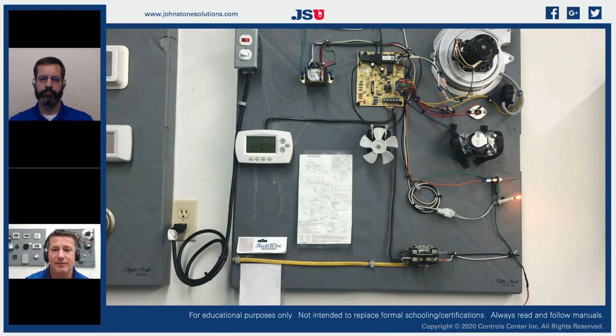So what I have done is I have calculated out the values that we would need for our resistance and the peak applied DC voltages and peak applied current that we want flowing, our electrons that are going to flow through the diode. And I created an electrical simulation for that so that I can apply a 1.5 microamp DC load onto my flame rod from ground. I looked at applying for a patent on it. It's very expensive, and I wouldn't really sell enough of them. But if you as educators have a piece of equipment in your lab that you don't want to hook gas up to, no big deal. We can simply do that with flame rectification.